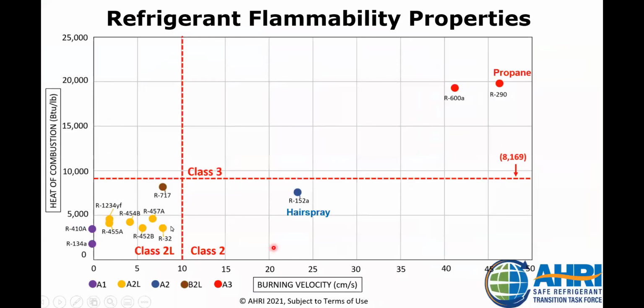To give you some scale to this, on this drawing on the bottom is how fast this stuff would burn. Up the left-hand side is the heat of combustion. We're usually over here on the far left side, meaning it doesn't propagate flame. Right? We're A1s. We're on the 0 line, right? Avoid all problems. The new A2L bucket is this dotted line right here. And our new A2L refrigerants are the ones that are in this orange, yellow, gold, whatever you want to call that, right? Those are our new A2L refrigerants.